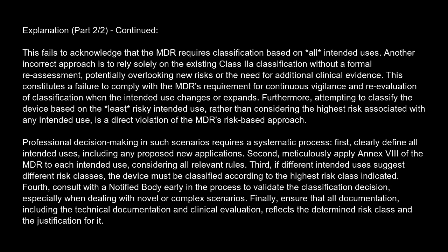Second, meticulously apply Annex Roman 8 of the MDR to each intended use, considering all relevant rules. Third, if different intended uses suggest different risk classes, the device must be classified according to the highest risk class indicated. Fourth, consult with a notified body early in the process to validate the classification decision, especially when dealing with novel or complex scenarios. Finally, ensure that all documentation, including the technical documentation and clinical evaluation, reflects the determined risk class and the justification for it.